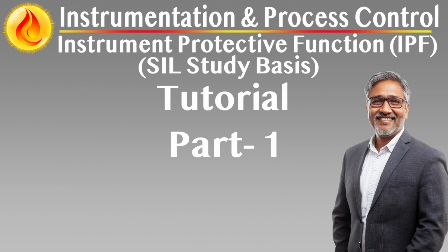Consequence categories. To support consistent SIL allocation, consequences are grouped into standardized categories based on the nature and severity of the potential impact. These typically include personnel safety: minor, first aid injury or reversible exposure; moderate, lost time injury or short-term hospitalization; major, permanent injury or fatality to one individual; catastrophic, multiple fatalities or large-scale personnel exposure. Environmental impact.